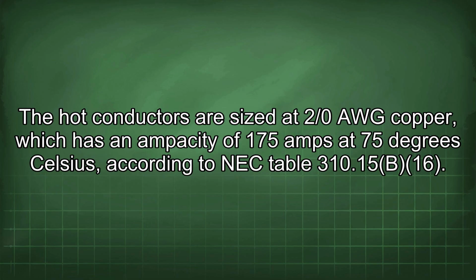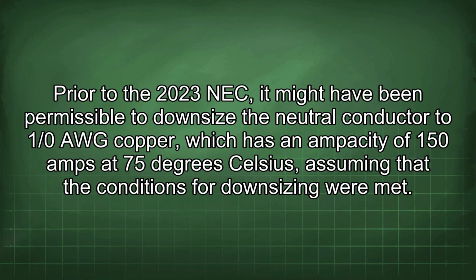The hot conductors are sized at 2/0 AWG copper, which has an ampacity of 175 amps at 75 degrees Celsius according to NEC Table 310.15(B)(16). Prior to the 2023 NEC, it might have been permissible to downsize the neutral conductor to 1/0 AWG copper, which has an ampacity of 150 amps at 75 degrees Celsius, assuming that the conditions for downsizing were met.